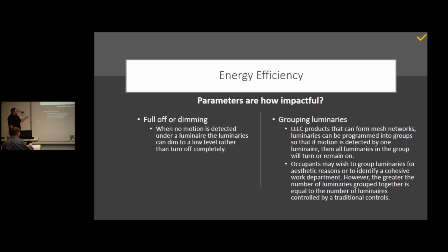Grouping luminaires. If you can form mesh networks, luminaires can be programmed into groups so that if motion is detected by one luminaire, all the other ones turn on. You can also do that in specific sequences. Say you're in a warehouse driving your forklift, you turn down the row, and the first light picks you up. It's going to send a signal to the next three: the next one should go to 80%, the one after that to 60, the one after that to 40, and it's just going to track you. As you move through that hallway or corridor, the light behind you is going to dim and then turn off as you continue down the space.